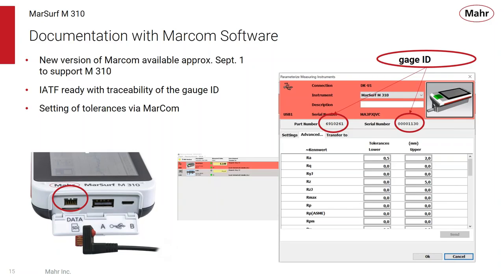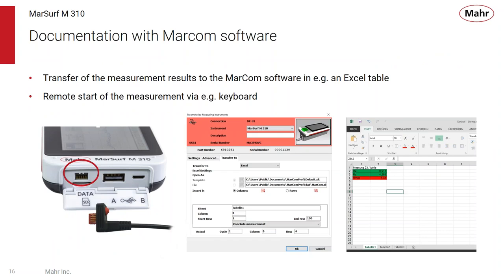You can see on the right-hand side what a setup screen looks like for Marcom or MarConnect. There's a part number and a space for a serial number, and this is the gauge ID number. So now, whenever a piece of data is recorded, you can also have the gauge ID number come along and be part of the measurement results, documenting for yourself what instrument made the measurement. Here is an example where we've put the duplex cable into the system. We can transfer the instrument data into an Excel table, and you can document the gauge ID and the results.